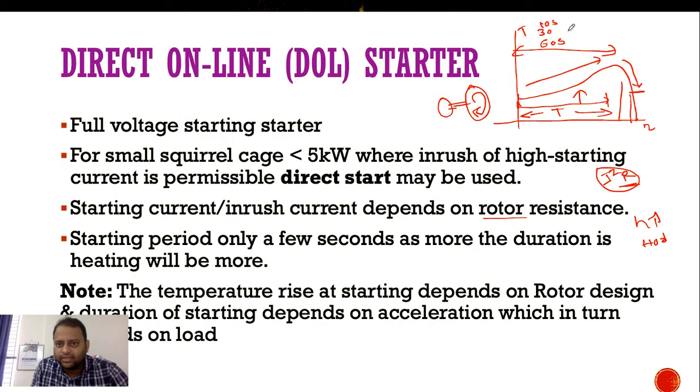10 seconds is good. If the time increases from 10 seconds to 60 seconds, the heat losses also increase, so your motor can get damaged very easily. You are also not getting airflow, because when you are near synchronous speed, your rpm can be 1450 rpm, and the airflow from the fan of the motor will be good inside the rotor and the stator. But at the starting condition, from 0 speed to say 1000 rpm, the amount of airflow inside the air circuit of the motor is less. That is a good cause of increasing the temperature.